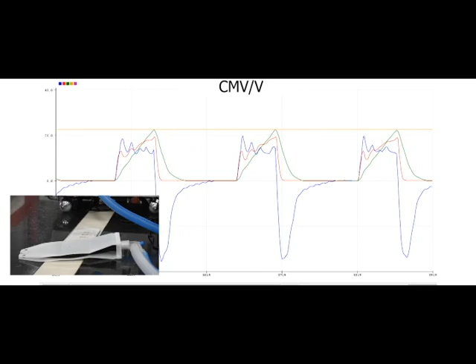After this, let me show you the flow situations for controlled mechanical ventilation of pressure control type, that means CMV-P type. Here, let me take the settings of 25 centimeter of water column as pressure control, respiratory rate RR as 10, and inspiratory to expiratory time ratio as 1:2. Okay, let me set my ventilator in that mode.